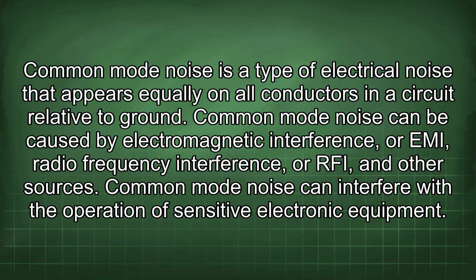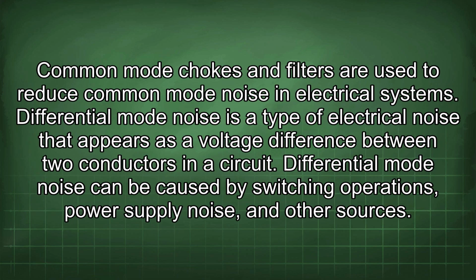Common mode noise is a type of electrical noise that appears equally on all conductors in a circuit relative to ground. Common mode noise can be caused by electromagnetic interference or EMI, radio frequency interference or RFI, and other sources. Common mode noise can interfere with the operation of sensitive electronic equipment. Common mode chokes and filters are used to reduce common mode noise in electrical systems.